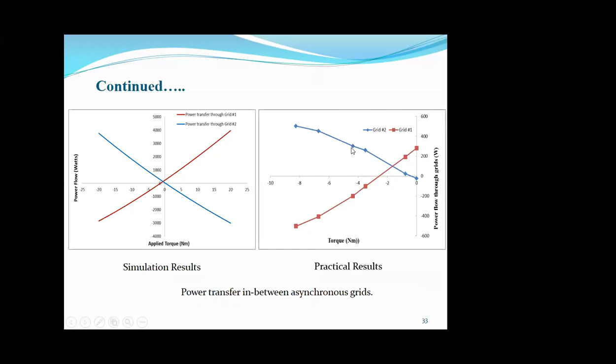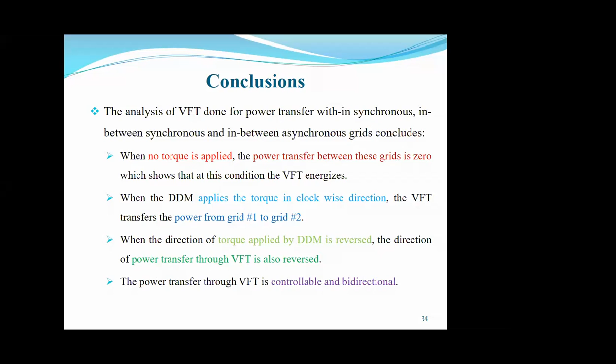First, when no torque is applied at the rotor of the VFT, no power flow takes place between the grids. When torque is applied at the rotor of the VFT in one direction, power flow takes place from grid 1 to grid 2. As the direction of torque is reversed, the direction of power flow also reverses. From this, I am able to say the power flow through the VFT is controllable and bidirectional.